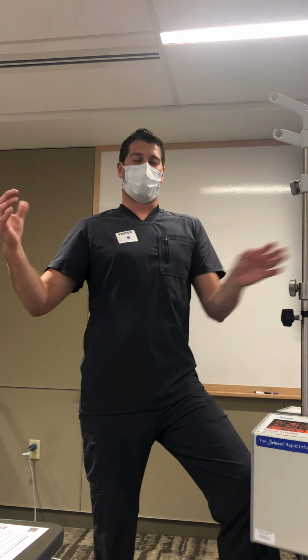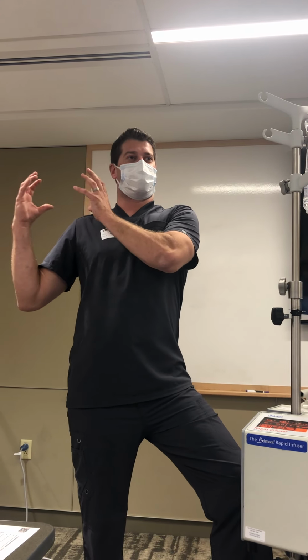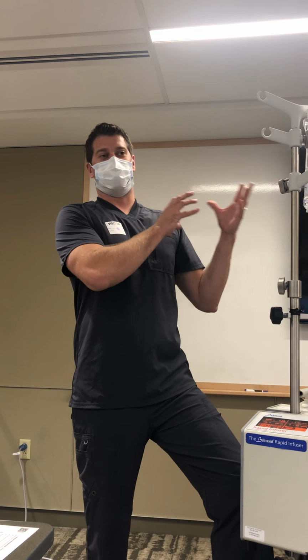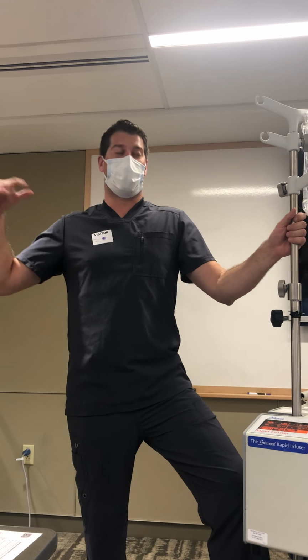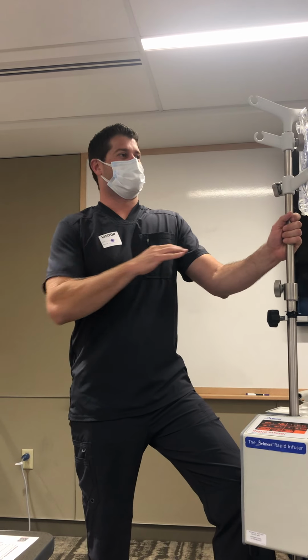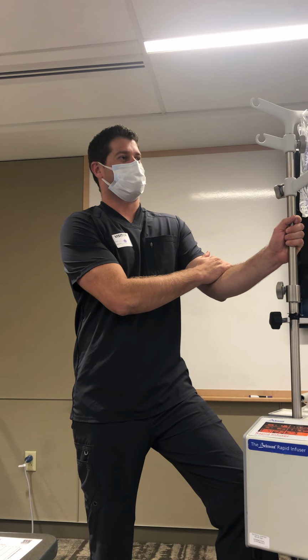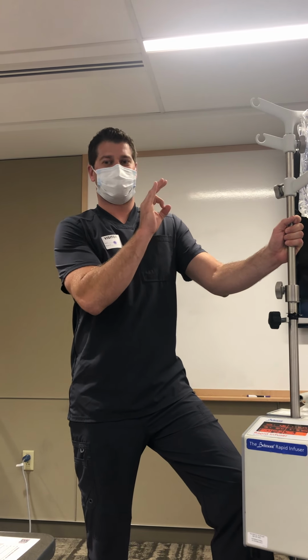But the reason I mention all these things is because the machine does not care where the back pressure comes from. It's going to sense it, it's going to regulate itself, and therefore maybe not give you the desired rate that you're looking for or what you feel you should be getting. But the more you know about all the factors up front and what the byproduct is on the back end, the more you know you need to change to get that desired rate. Hopefully that makes sense. Good.